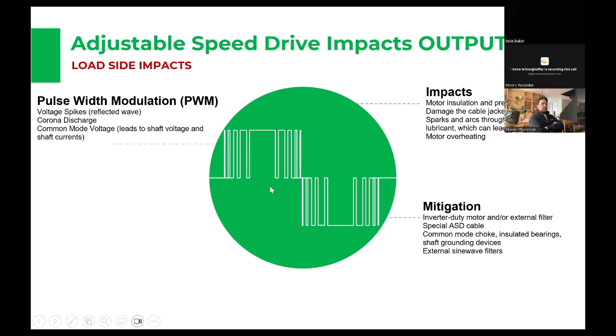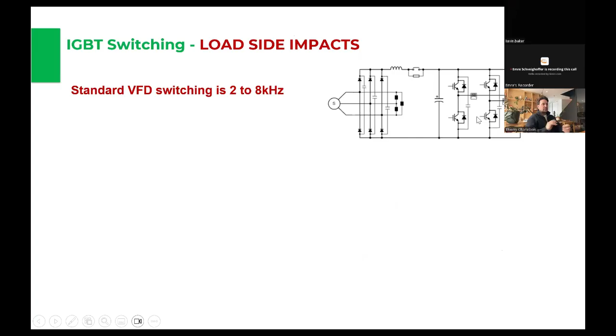Perfect. So here's a schematic of the VFD. And we have power coming in on the rectifier side. Here's your DC bus. And of course out to the motor. And these switches here, the IGBTs, they have an algorithm that allows them to switch in tandem, in pairs, and simulate this square wave going out to the motor, right? So that could be basic for some, it might be new for others. And what happens is this signal, depending on how long your cable is, it'll start to distort on this back end towards your motor.